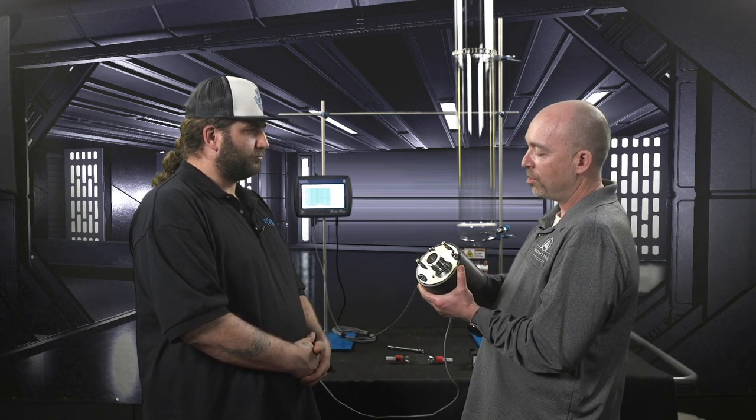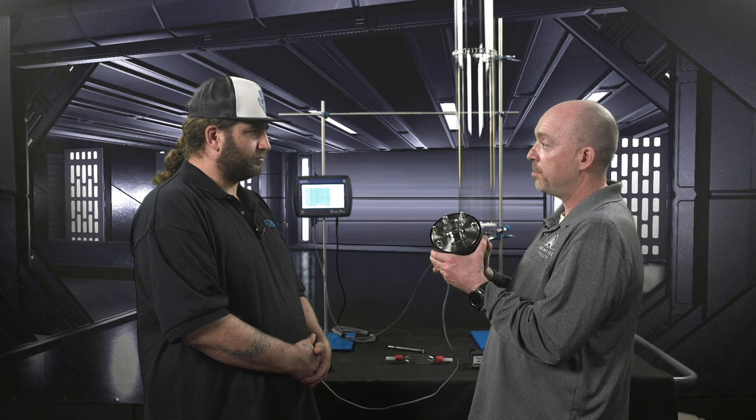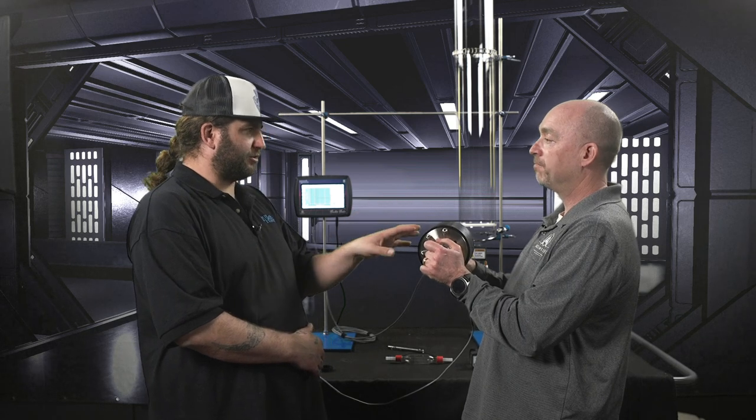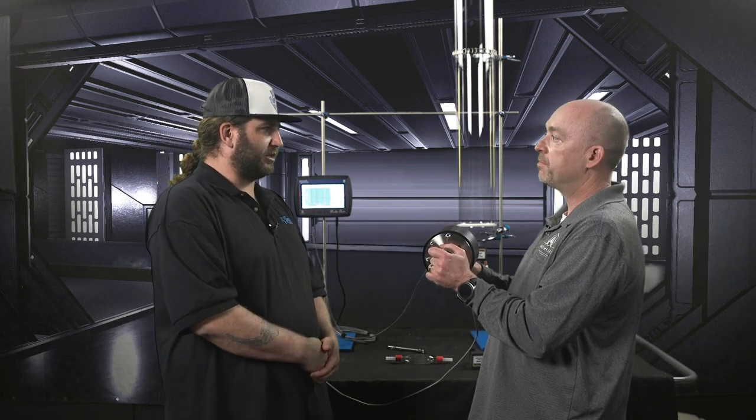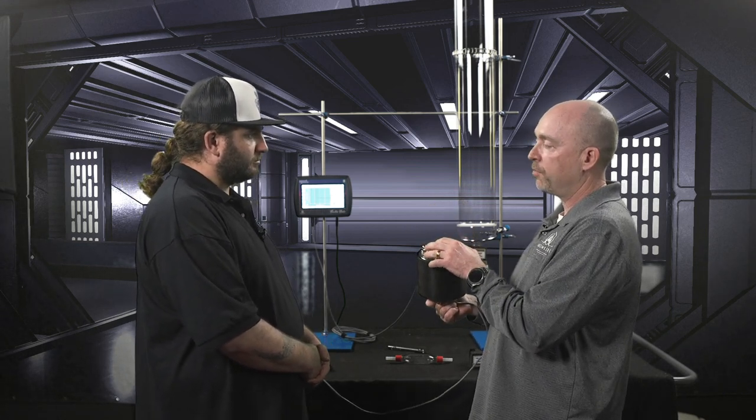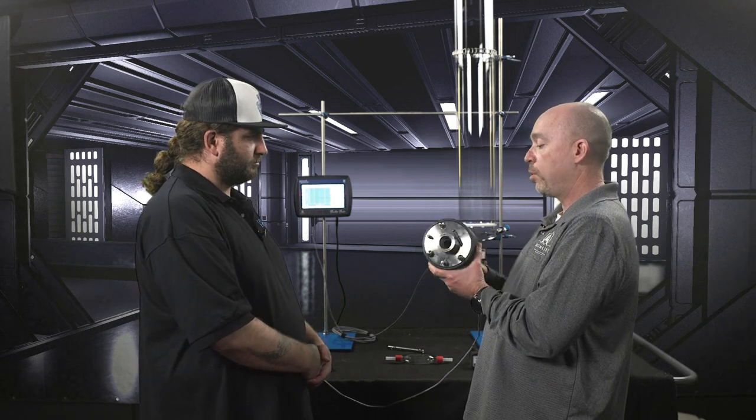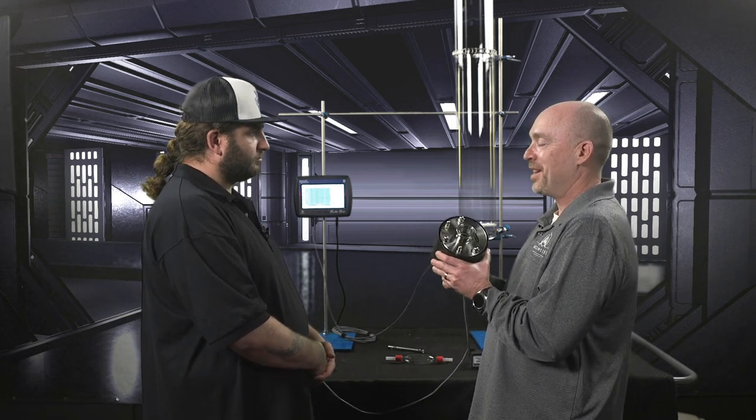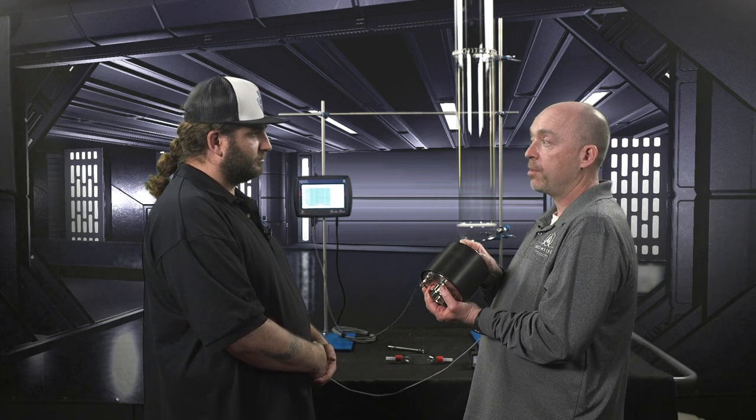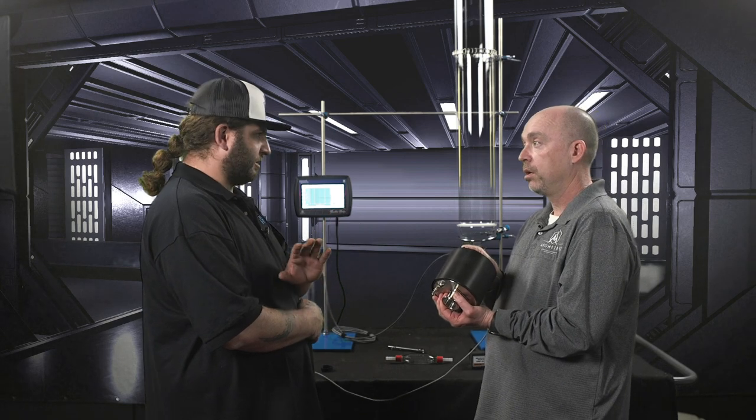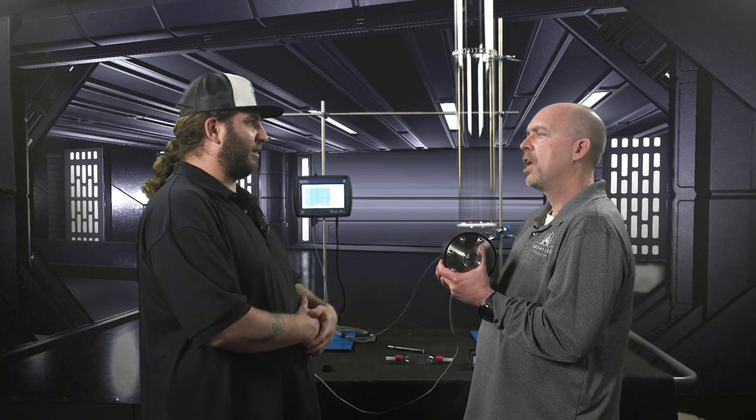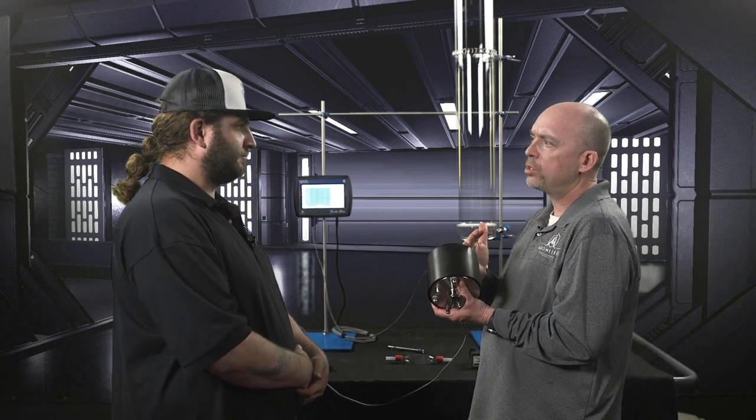So this has this external piece and it's quite a solid piece. That way, which also in turn helps seal from outside chemicals, hydrocarbons, other things from getting inside as well too. That's right. So protects the users. We've actually tested this. We certify it for 240 PSI because that's what the sight glass inside is rated for. But we've tested this up to 800 PSI. So we feel pretty comfortable that this device is going to really serve the hydrocarbon industry really well.